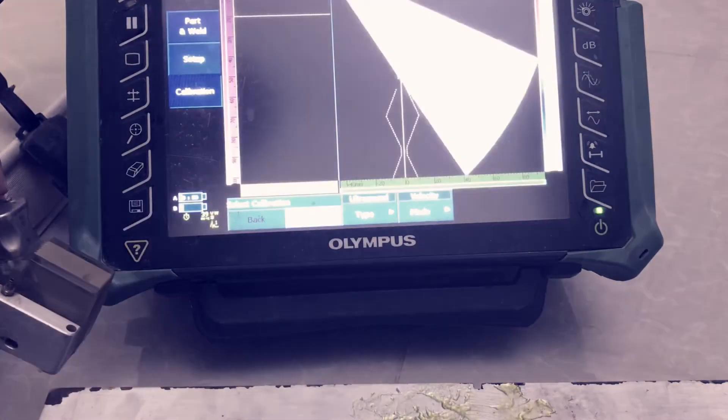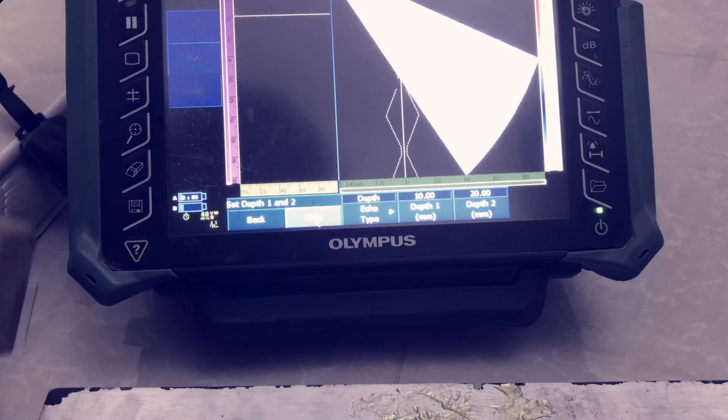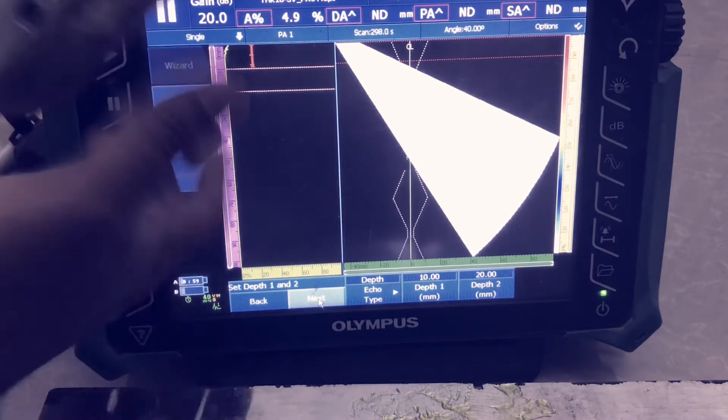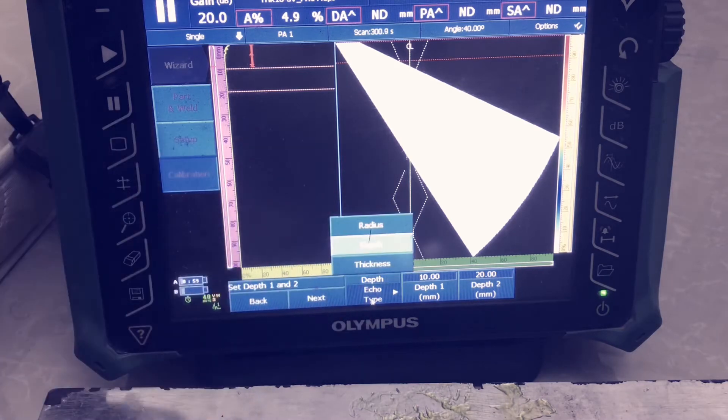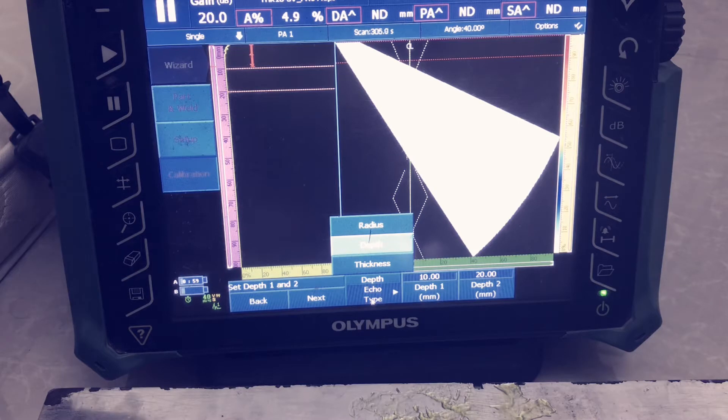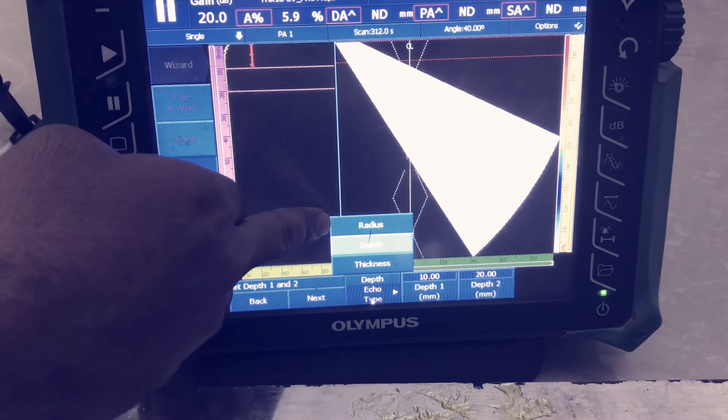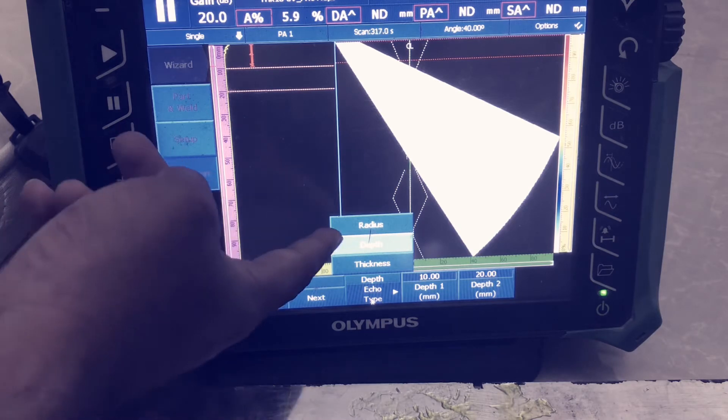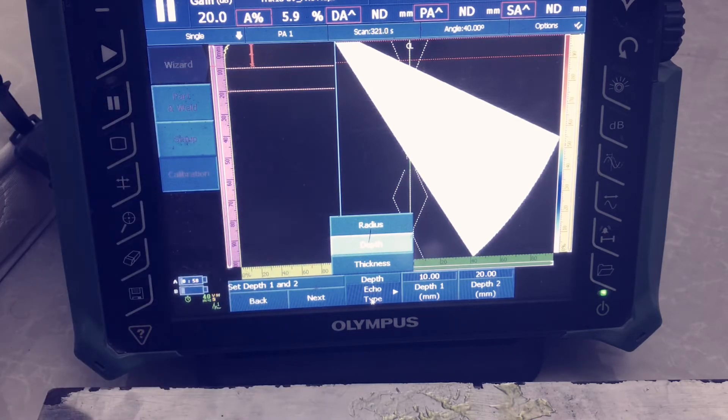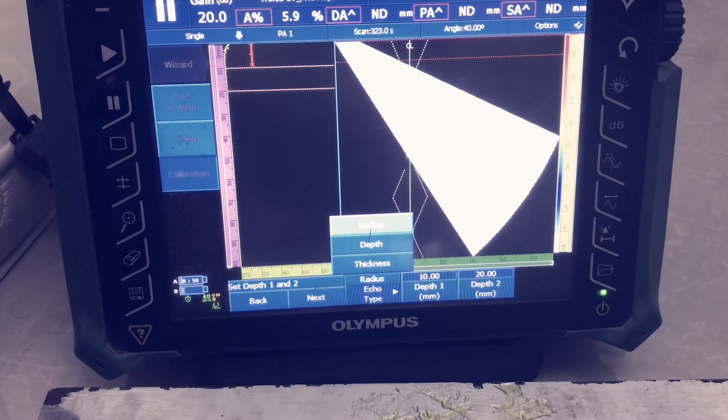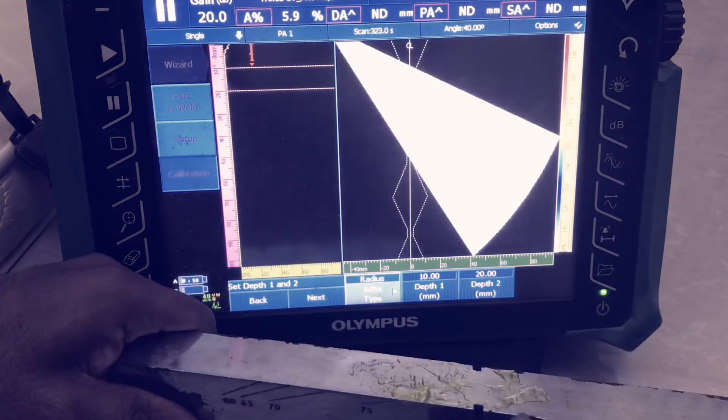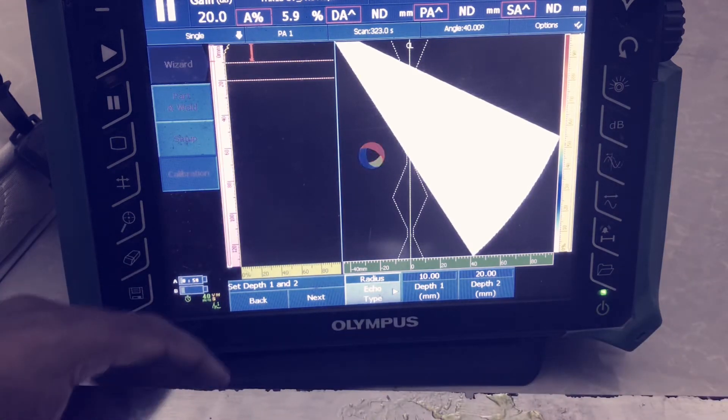First we complete the options parameters. See here, echo type, radius option, depth option, and thickness are available. Now we are using V1 block, so we can choose radius. If you have standard block, there is a side hole there, we can choose depth and thickness also. It depends upon the availability. Now we are choosing radius because this is the radius in V1 block.